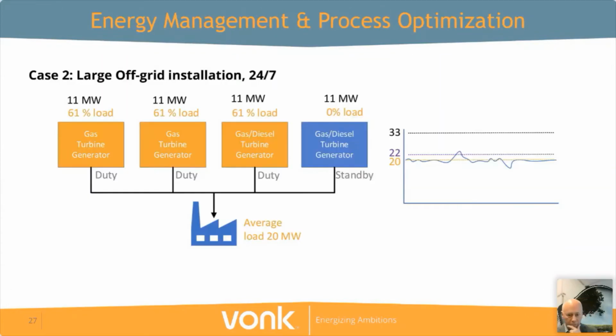A larger example, the load is quite a lot higher here. The industrial facility needs 20 megawatts of energy. This is now being supplied by 2 gas turbines and 2 dual fuel turbines. 3 of them are running. However, the load is not always 20 megawatts. There will be peaks. And in this case, you need the 3 generators to cover those peaks, because 2 alone, which only come up to a maximum of 22 megawatts, as you can see in the graph at the right, will not be enough. So you need the 3rd one.